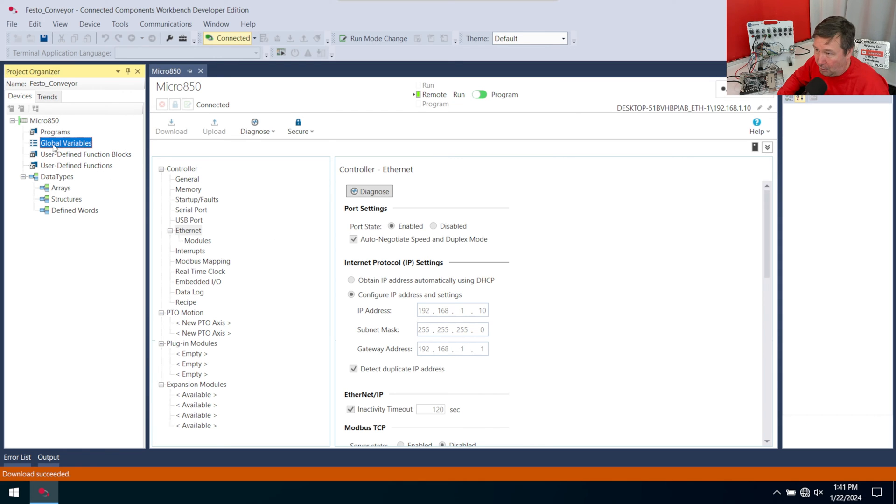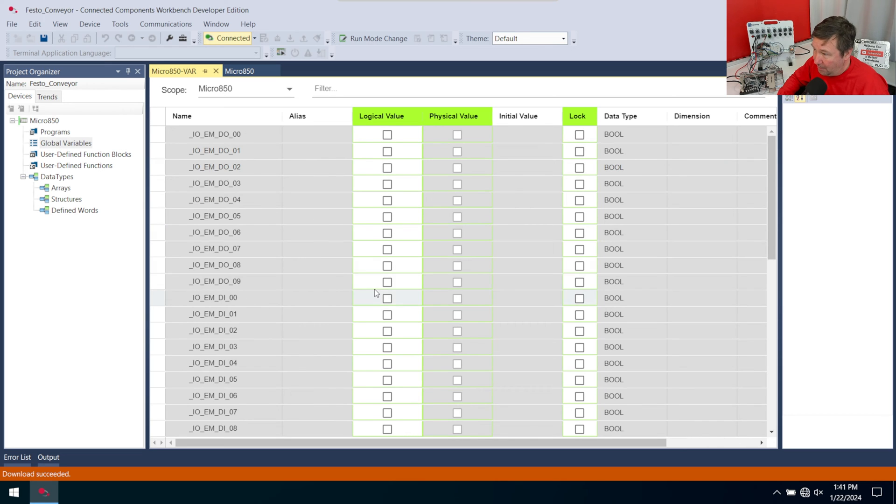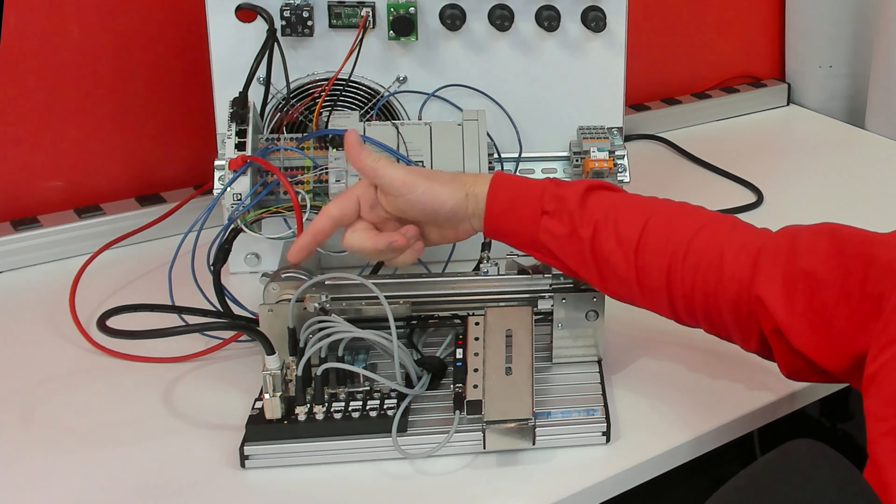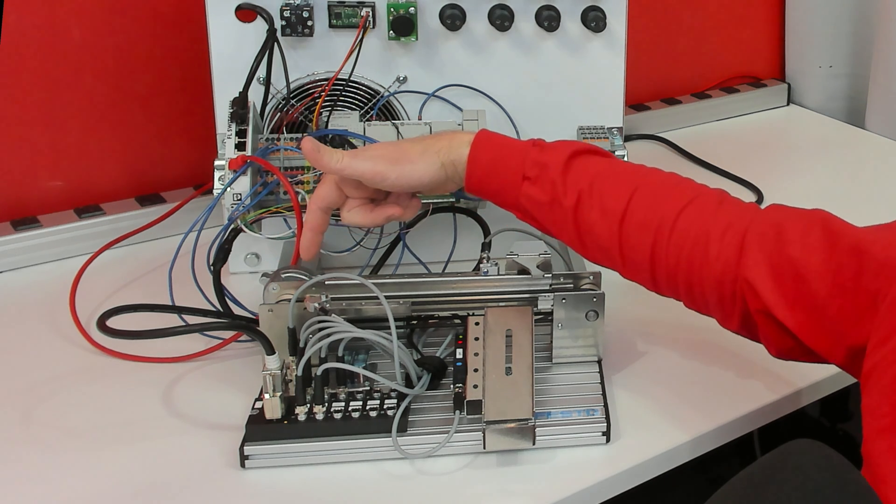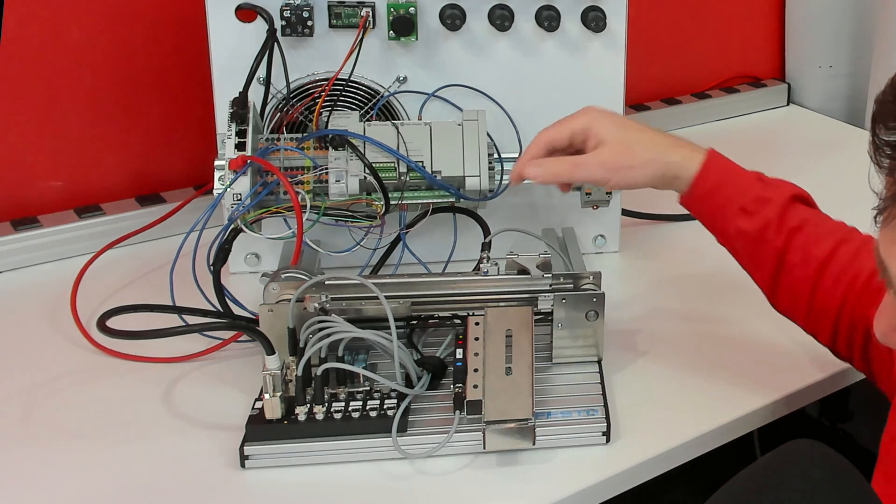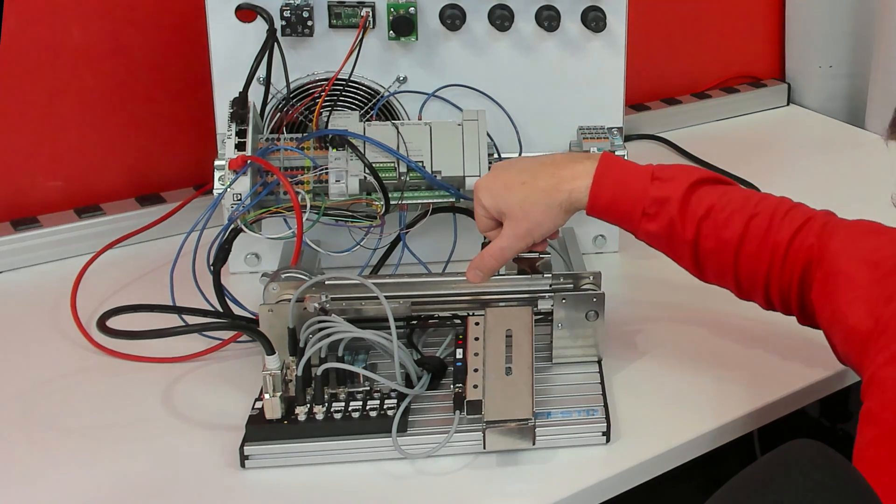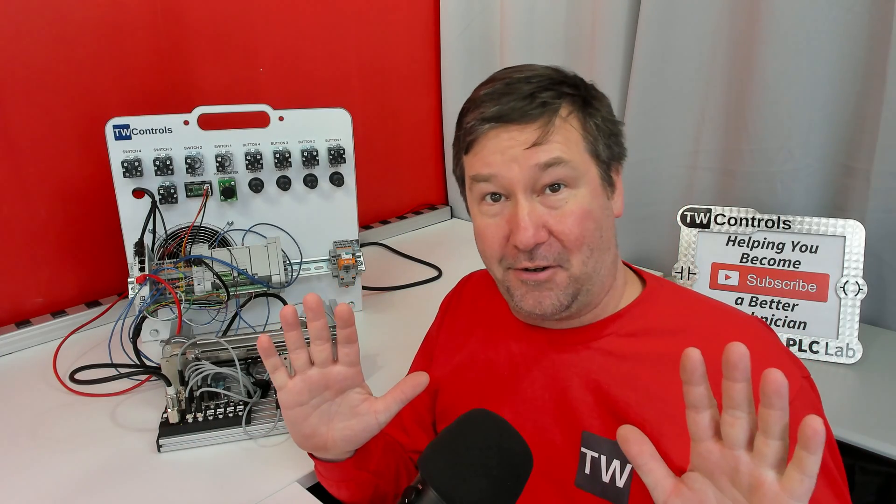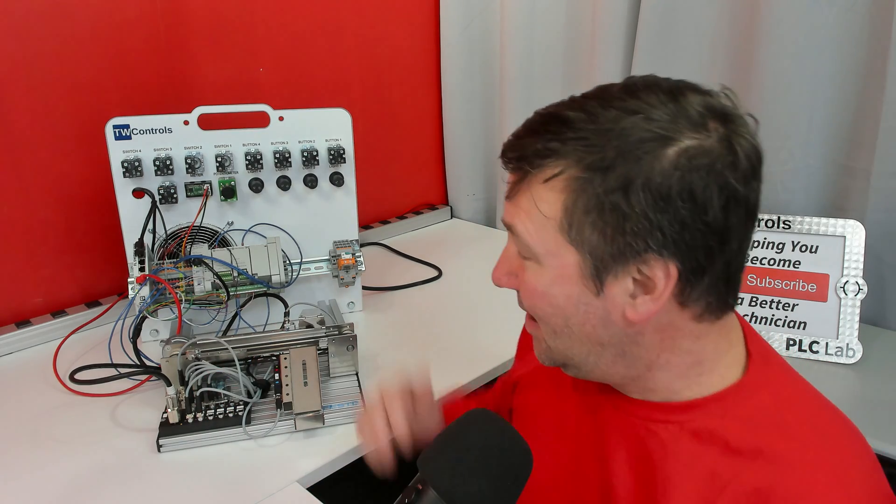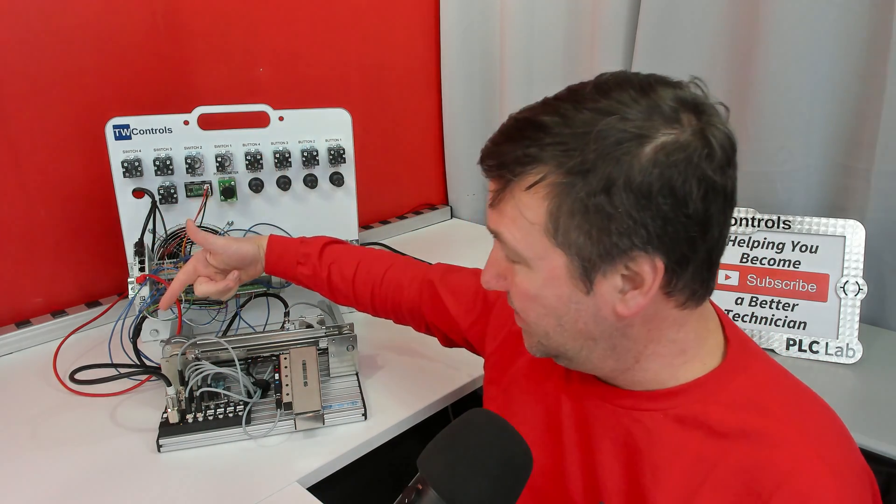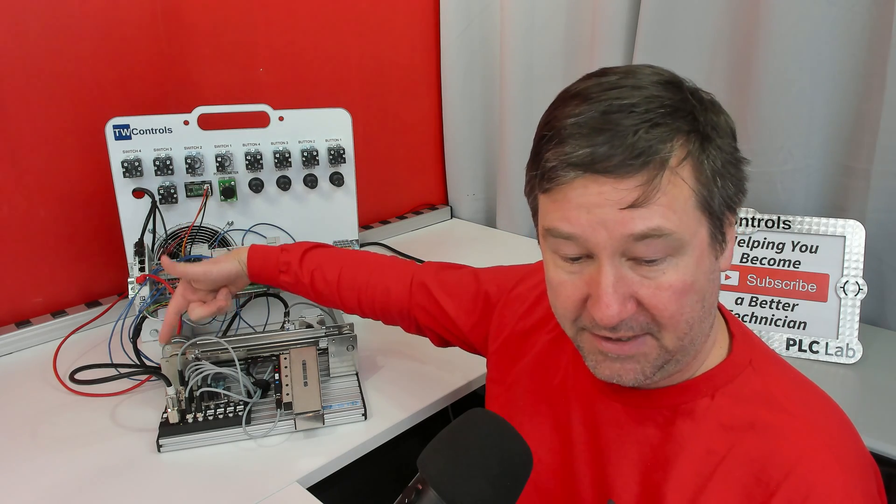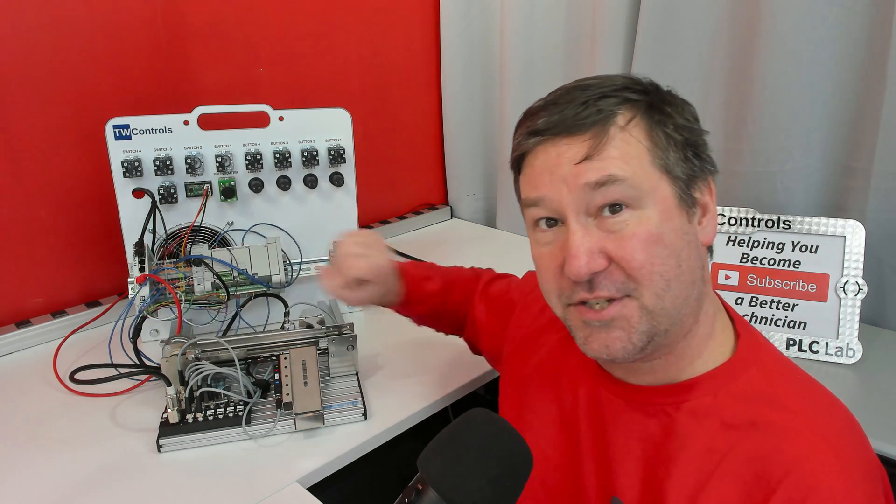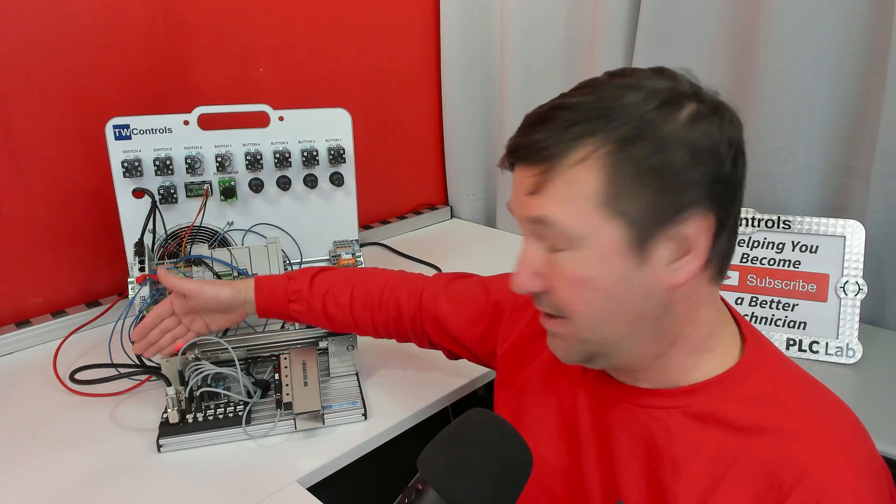All right, now let's open up our global variables. And we can see our inputs and outputs. And we've wired to input zero and input one. And we're going to start by putting our finger over top of the sensor on the front of the trainer. And when I stick my finger in front of it, we are getting inputs. Now I'm going to stick my hand over top of the other one. And we're not getting it. Now hold on before you start grabbing your wiring and jerking something out. This is part of the learning exercise. So the sensor on the front is an optical sensor. So when I stick my finger in front of it, you can even see a little bit of the glow of the light. So it's shining light out and looking for a reflection of something.